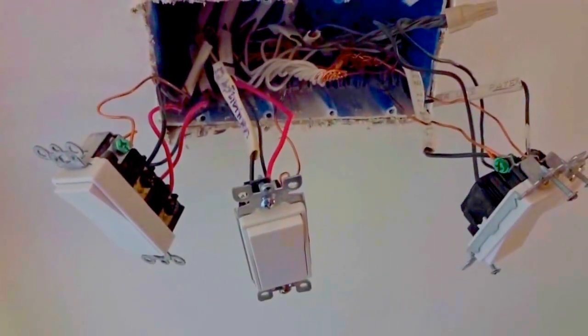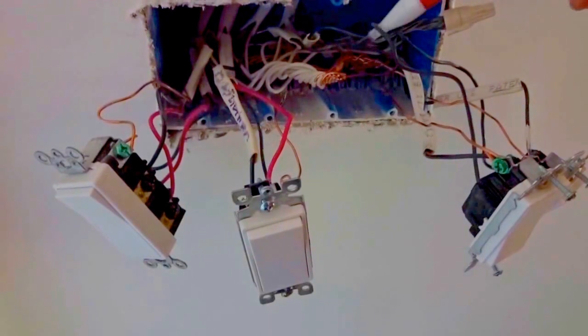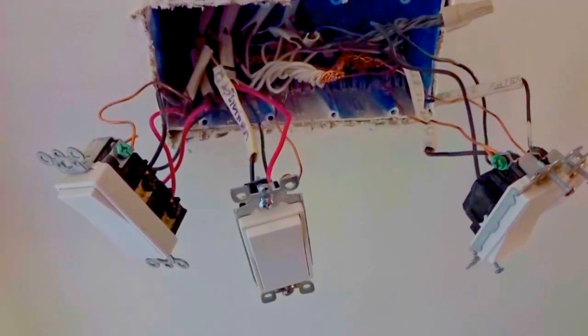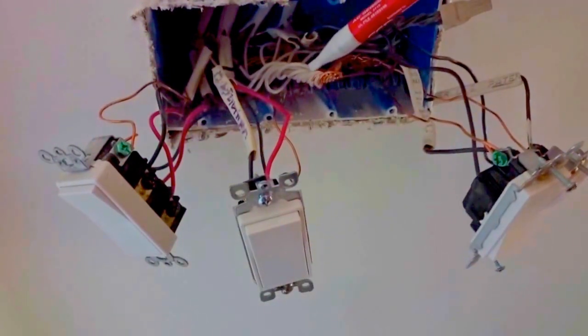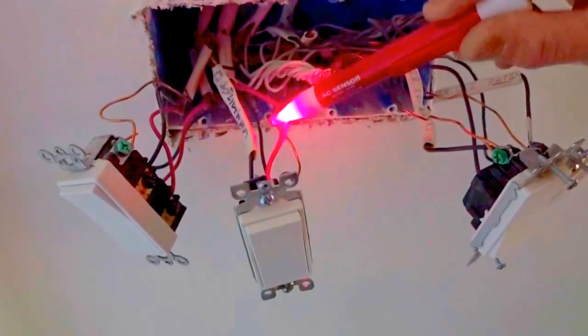I found by turning off one breaker at a time that we have three different circuits in this box. All the neutrals are made up under one wire nut. One of these circuits is still on.